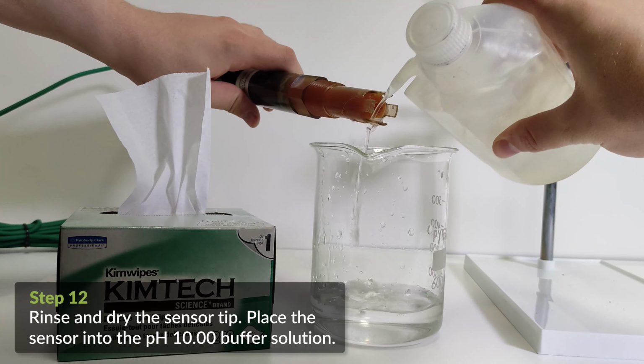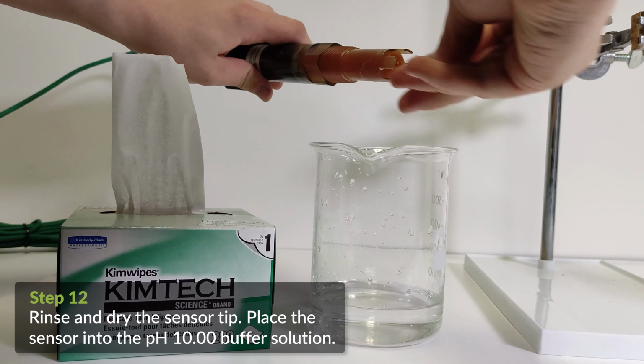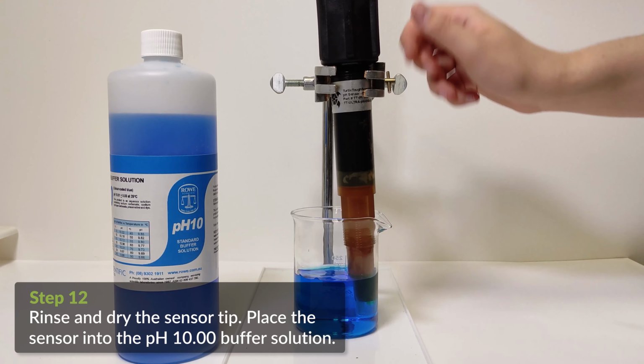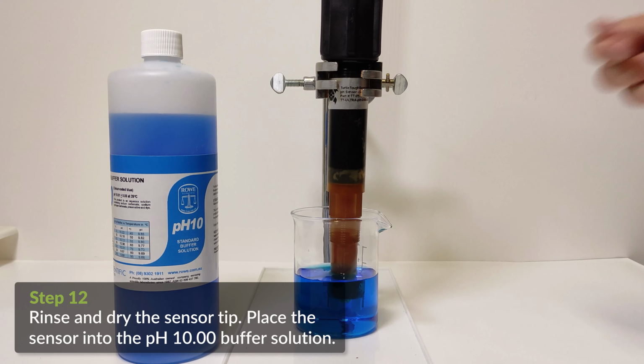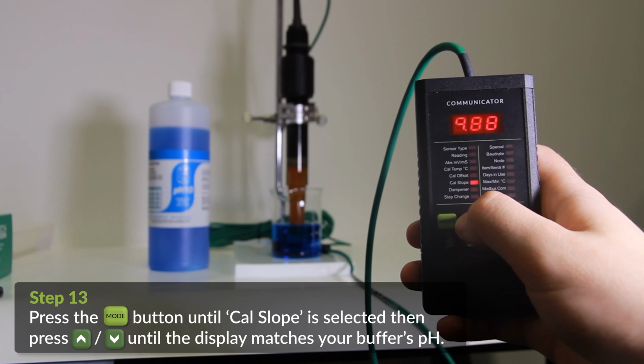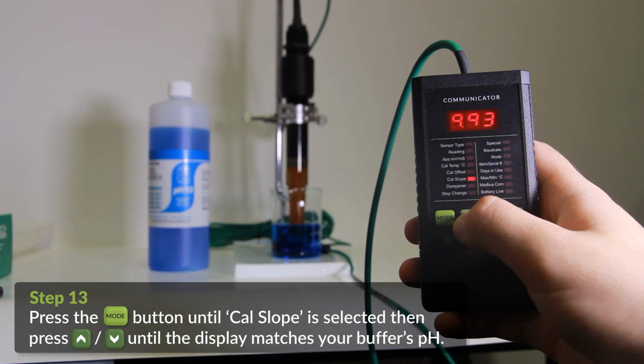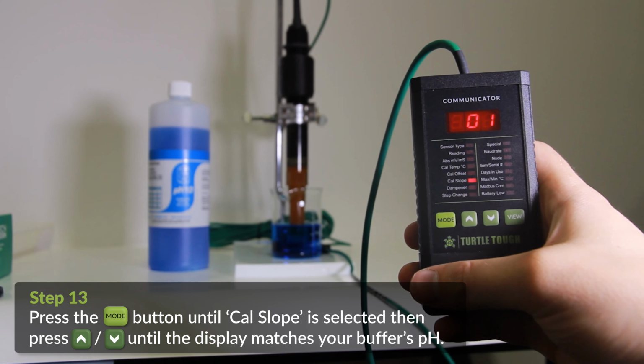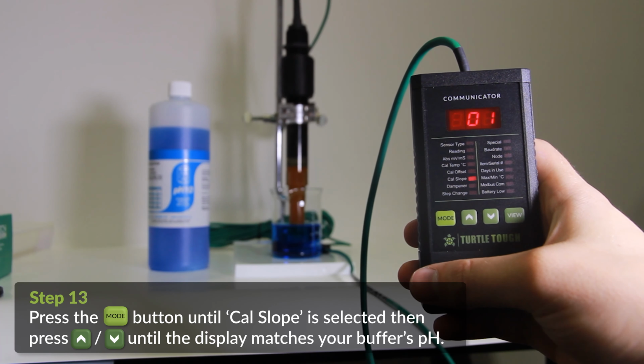Remove the sensor from buffer 4, rinse and pat dry again to start the third calibration. Place the sensor into the buffer 10 solution to establish the pH sensor's alkaline slope. Allow a few seconds for the reading on the HFC to stabilize. Once the reading is stable, press the up and down arrows until the value displayed matches the buffer 10 pH value. Now you are finished.